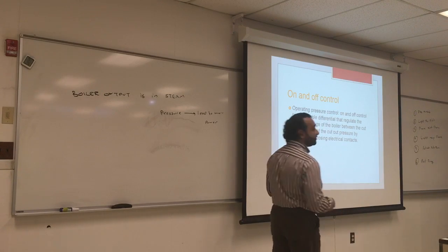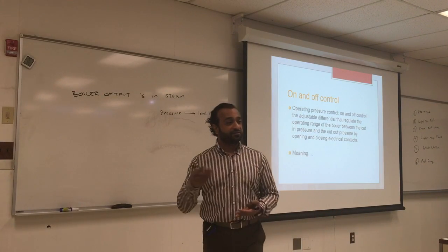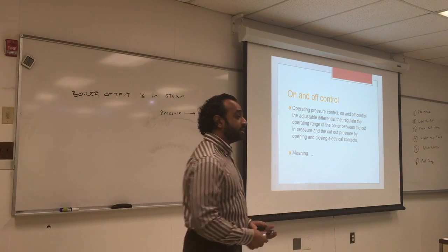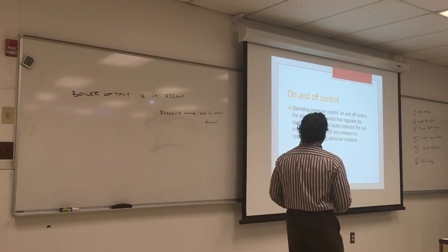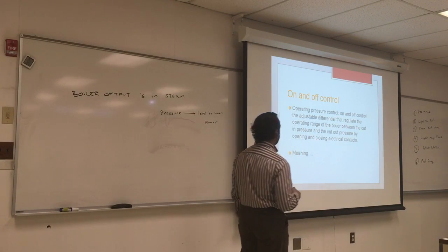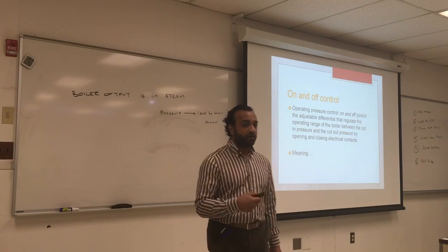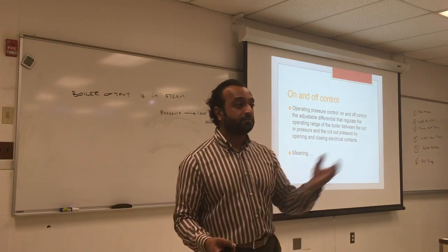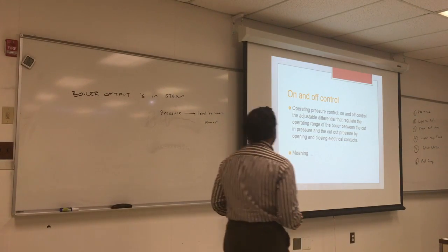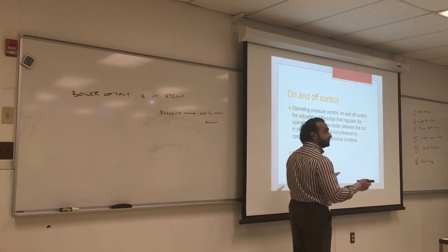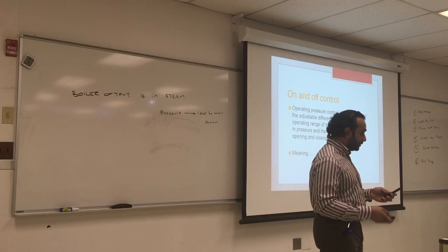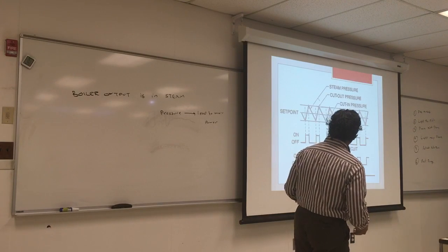So on and off: we turn the fire on, we have steam; fire off, no steam. More steam and less steam — it's an on and off situation. We adjust the differential that regulates the operating range for the boiler. The more fire you put, the fire will eventually become related directly to the steam. So we have a cut-in pressure and cut-out pressure. And sometimes we have steady flow.